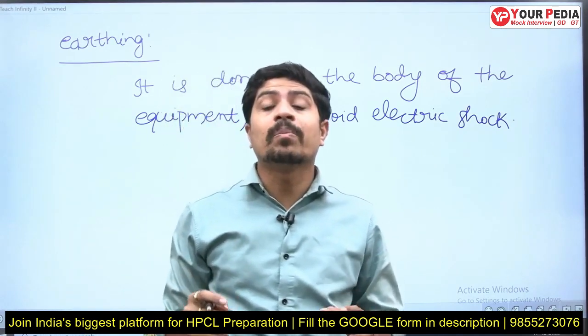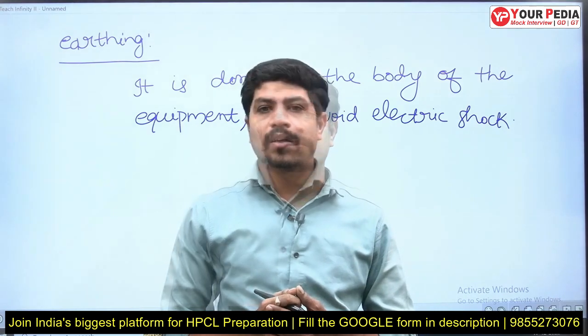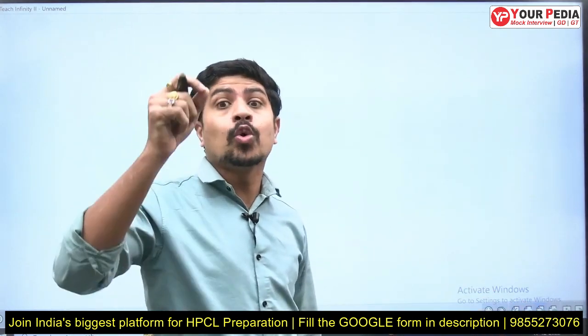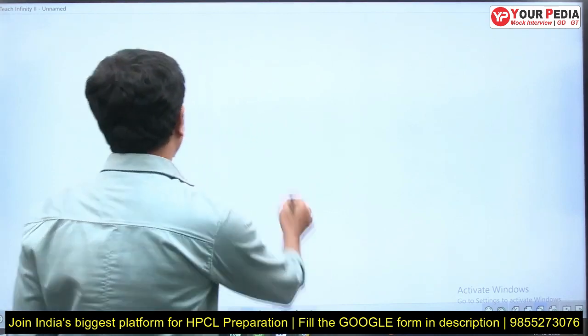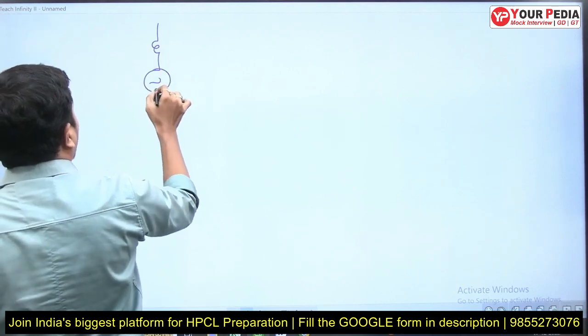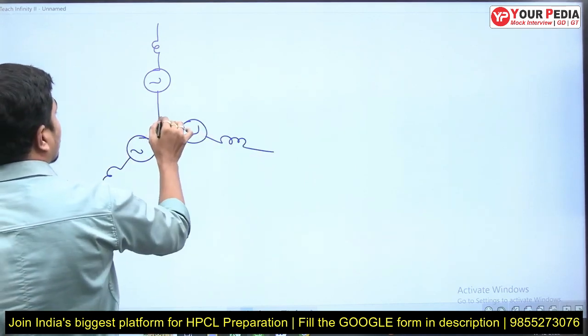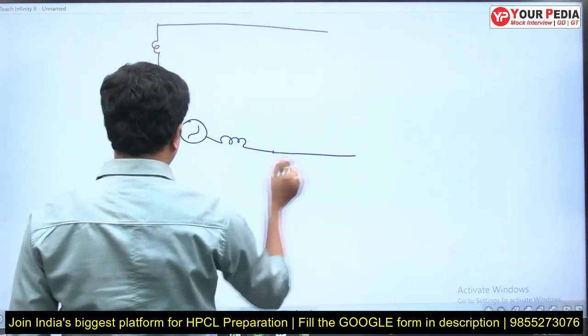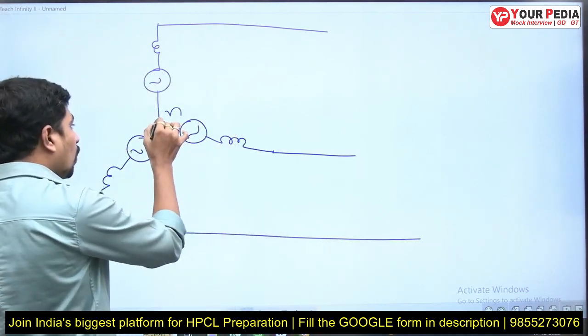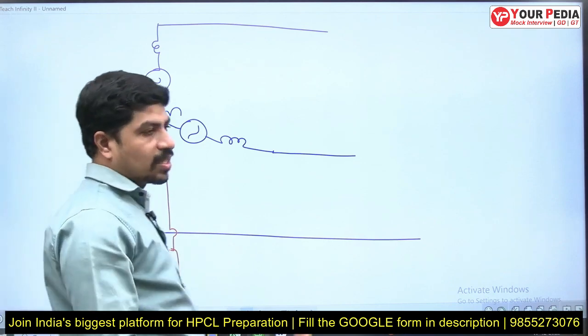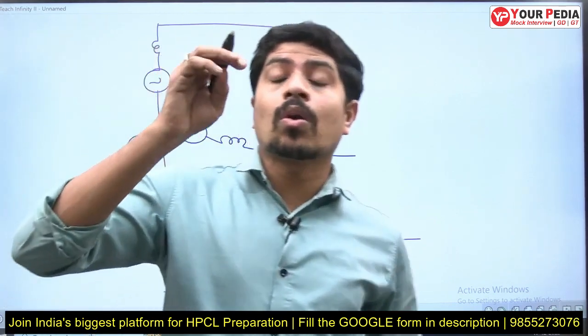Now let's understand what grounding is. Grounding is also connecting to the ground, but it specifically means connecting the neutral of the generator to the ground. I have a three-phase synchronous generator — this is the neutral of the generator. If we connect the neutral of the generator to the ground using either a resistance, reactance, Peterson coil, or solid grounding (where resistance equals zero), this process is called neutral grounding.